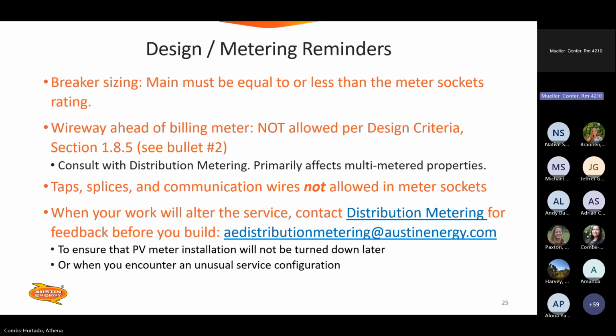Also a no-no is a wireway, colloquially known as a gutter box, ahead of the billing meter. This is not allowed per our design criteria. If you see, for example, a duplex where there is a gutter or wireway ahead of the revenue meter, not the solar meter, but the revenue or billing meter, then that's a service that will require work prior to a PV system being installed. Taps, splices and communication wires are not allowed in meter sockets. You just have to have straight uninterrupted conductors going to all your terminals in any of our meter cans.